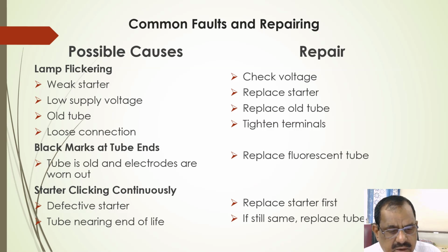Then if, after replacing the starter and the fluorescent lamp, you still have a problem and it is still not working, then you check the lamp holders where the pin is sitting. Check whether it is sitting properly and making contact or not. Sometimes, because of the heat, the property of the holder material is finished, and because of that it will not make proper contact. In that case, you have to change the lamp holder. Check both the holders, and if both are defective, replace them.